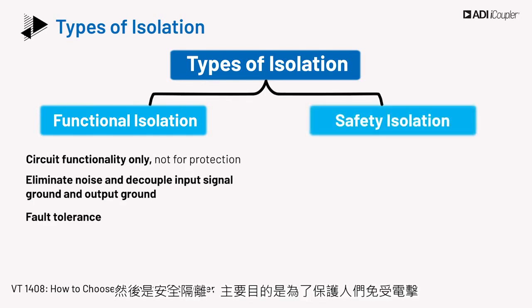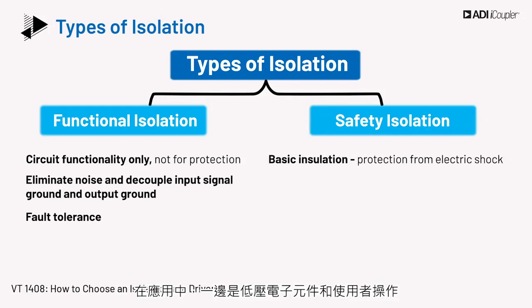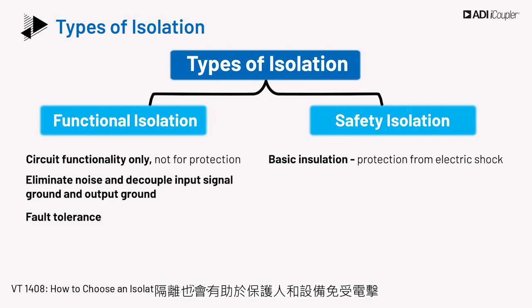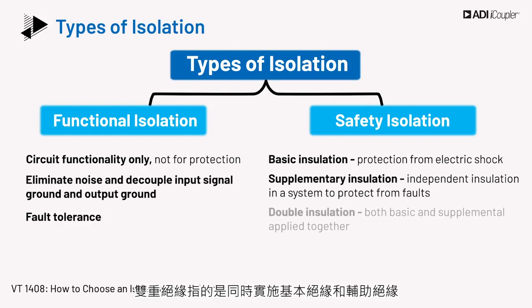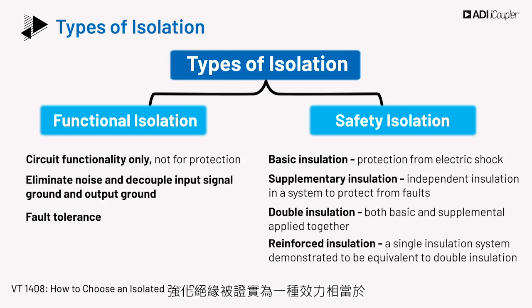Then there is safety isolation. This is required primarily to protect people from electric shock. There is low voltage electronics and user operation on one side and higher power levels at the switches. Isolation also helps protect people and equipment from electric shock. Apart from basic insulation, supplementary insulation may be present in a system to protect against faults. There is double insulation, which is both basic and supplemental applied together. Reinforced insulation is a single insulation system, demonstrated to be equivalent to double insulation.